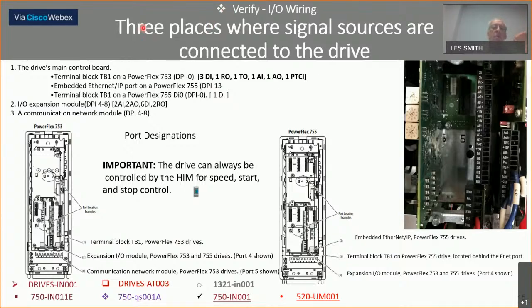The next subject I had, and that came out of the quick start, as you see by the symbol up here, was 3 places where signal sources are connected to the drive. I wanted the startup people to know where to look for what type of wires. And over here, the drive's main control board, since this is a slot drive, it's called DPI 0 on either the 753 and 755 is clear to the right over here. 753 has some I/O on it, and here the 755 has an Ethernet port on it, and it's got one input on the 755, and that's separate from the motherboard in the location. It's down here. You have to have a dental mirror to find it. But again, just knowing where to look for this.